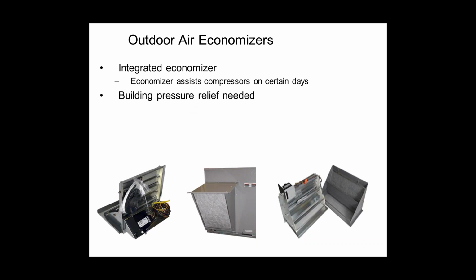I also have to figure out how I'm going to get air out of the building. If I'm going to open up this window with a fan on it and suck all this extra outside air in to cool my building, well, I'm going to pressurize the building. Where's all that air going to go? It can't just stay in the building, right? Otherwise, my building will blow up like a balloon, which it's not going to do, obviously. So if I do nothing and I run an economizer, I'll end up blowing the front doors wide open, and it'll be difficult to shut them and all that kind of stuff. So I have to have a pathway to get the air back out of the building.